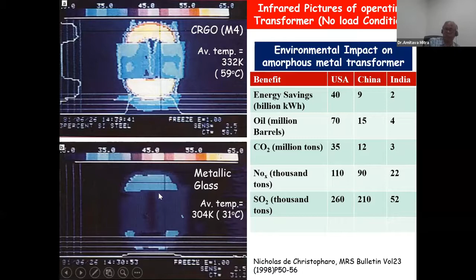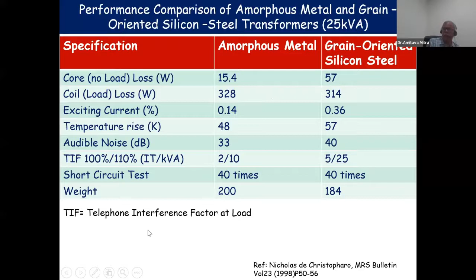There are already a lot of these transformers in use at different places. You can compare the core loss: the no-load loss for this one is 15.4 watts, and in the conventional case it's 57 watts. So you can understand the difference, though there is a slightly higher load loss because the amorphous alloy has high resistivity, so the load loss is a little higher. But considering it in totality, it is much more advantageous for transformer cores.